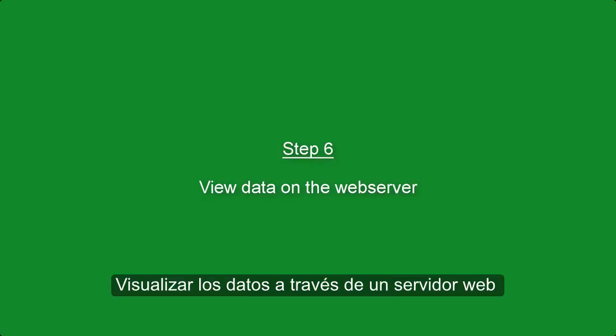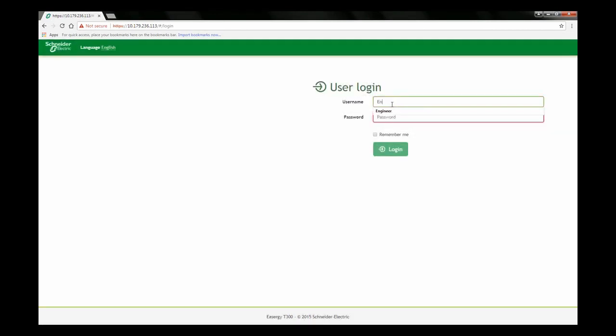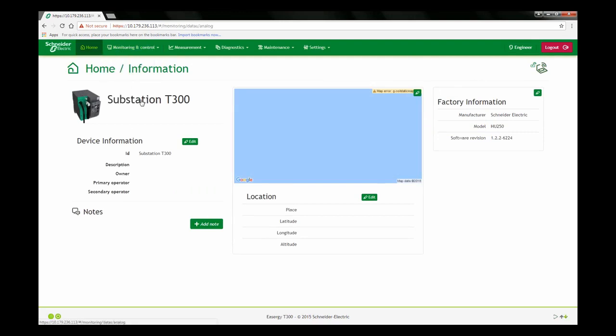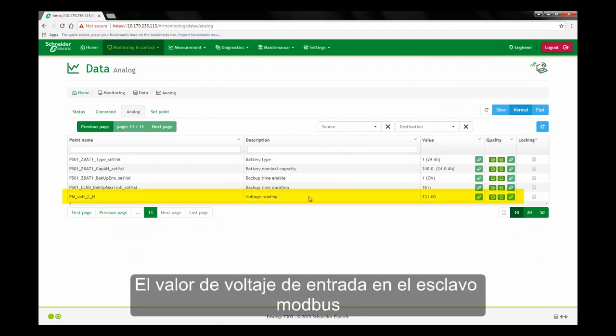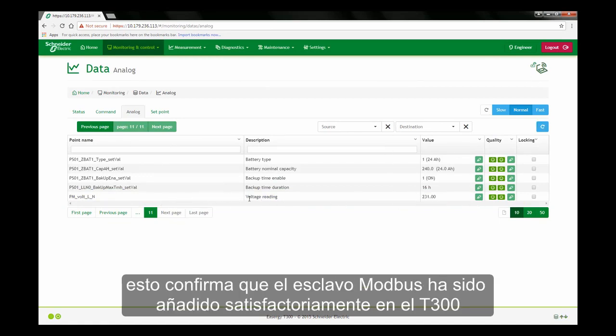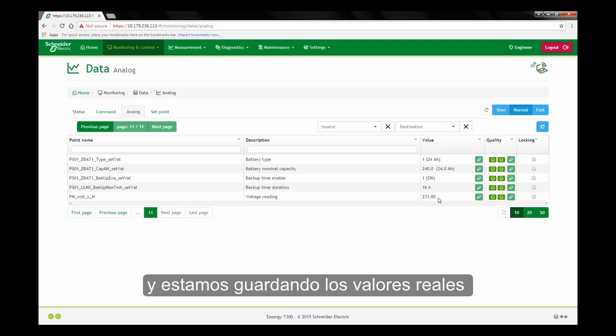Step 6: View Data on the Web Server. Log on to the T300 Web Server to view the Modbus Slave device data. The voltage input level on the Modbus Slave device as seen on the T300 Web Server is also 231 volts. This confirms that the Modbus Slave device was added successfully to the T300 and is communicating with the Easergy T300 with the correct data recorded.